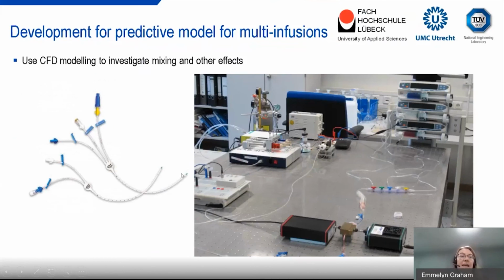We're also going to be using computational fluid dynamics modeling to investigate the mixing and other effects. This is a setup at Lübeck University, one of the partners. They've got some medical syringe pumps you can see in the back, with blue solution, red solution and clear solution, and these are the infusion lines that you would actually use in a hospital, and a mixing manifold that you would actually use. They're testing what the actual impact on the concentration is if we change the flow rate of one of the syringes. We've got a spectrometer set up at the bottom of the picture to be able to monitor the changes.